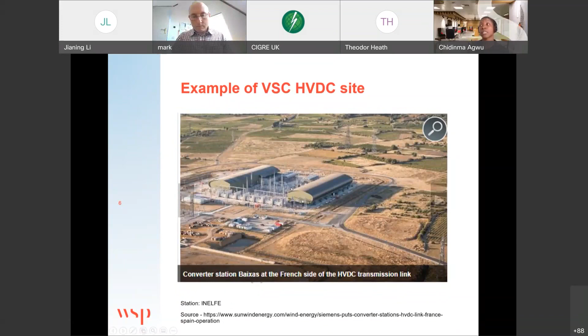Which then takes me on perfectly to the primary components of an HVDC converter station. The components for these sorts of stations are, again, dependent on your project and on the requirements, but these are the main components that every converter station will have, whether it's a back-to-back scheme or a transmission scheme. You're going to have your converter transformers. They're the noisiest things. Depending on the design of the station, you might have one massive three-phase transformer, or a lot of the time, especially with a VSC station, you have single-phase transformers, so you could have 3 per pole, 6 in total that would be operating.